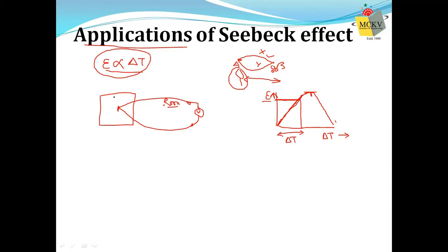Let us say this temperature is T1 inside the furnace and the room temperature is T2. So from the graph, you get T1 minus T2, because you know the EMF. And since you know T2, that is room temperature or whatever reference temperature, you know the temperature inside the furnace. So this is how you find out the temperature, and they are very, very accurate.